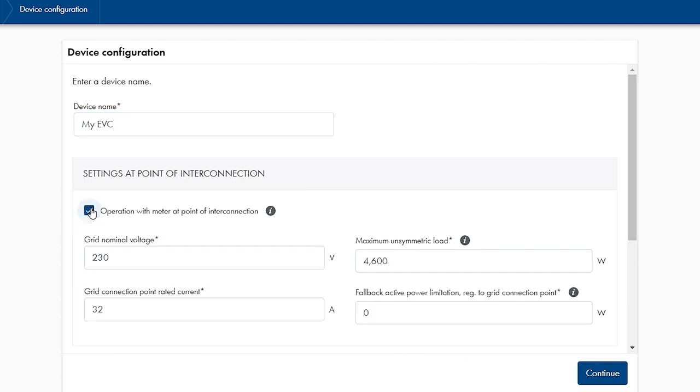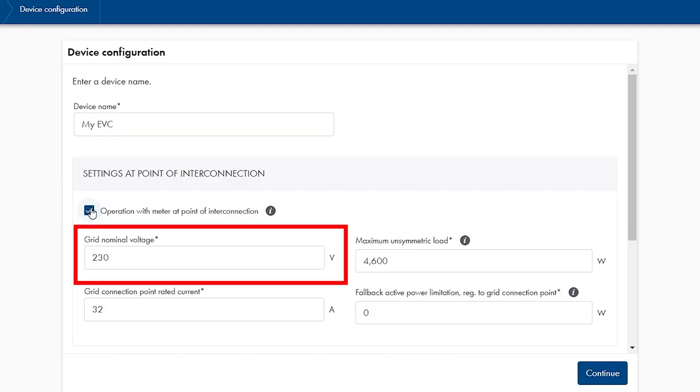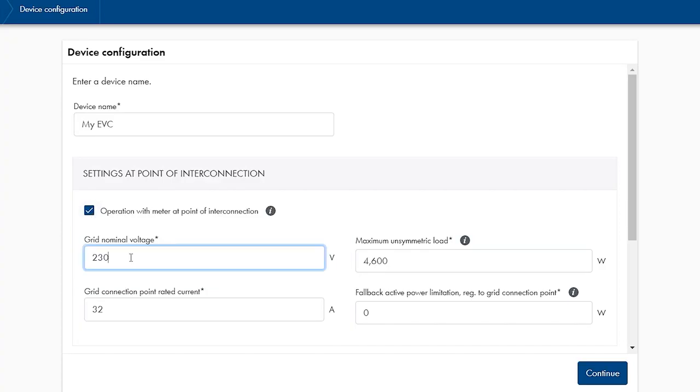Next, type in the nominal grid voltage. The voltage between phase and neutral is relevant. So even in a three-phase 400V system, 230V is correct.